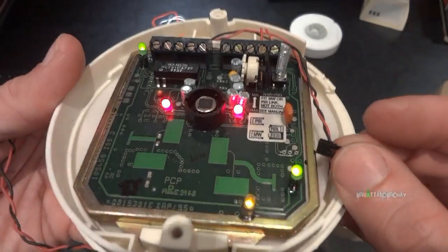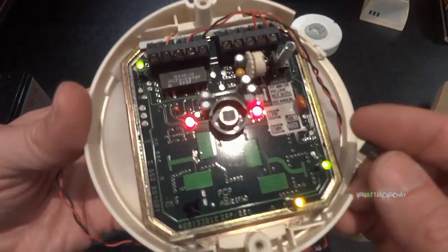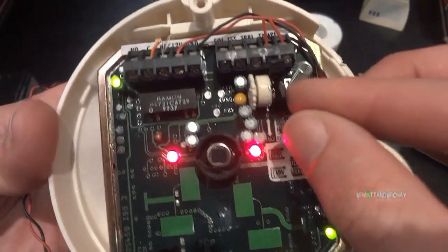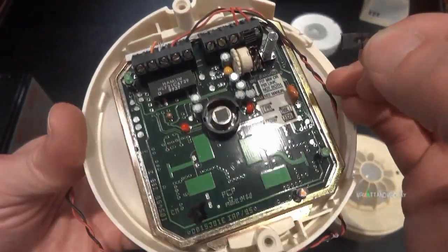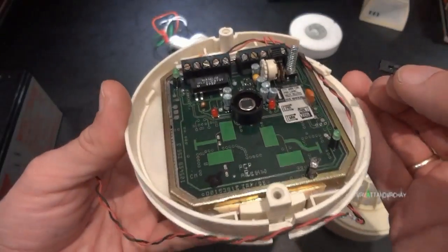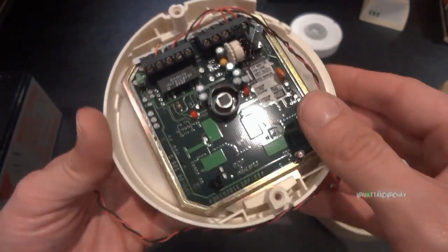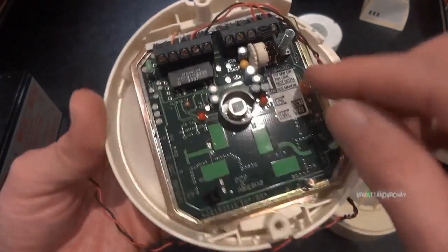One reason you might test them individually is if you can't see the LEDs from where you're walking and you want the control panel to bleep when it detects you. There's also a link that turns off the LEDs entirely — useful in a shop if you don't want people noticing the detector or figuring out where it works. Putting it on the trouble pin enables a watchdog circuit, so if either technology goes wrong it probably just flashes the red alarm LEDs — that's the trouble display.